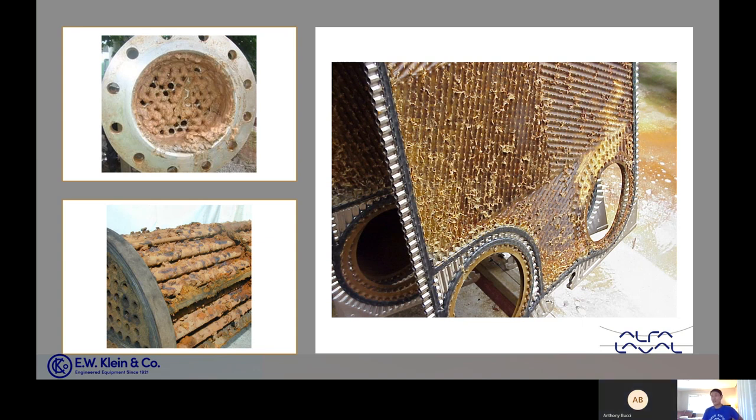So I actually had to clean some of these heat exchangers in my previous job. Like when it gets fouled up, they were tough. Like the ones I dealt with, it was like five feet long. So we had like five feet long full of tubes, full of gunk and gunky oil. It was tough to clean out, man. And if this gets fouled up on the shell side, I don't know. At least I didn't know a good way to clean it. It's like dropping it in a chemical bath and just let it soak. Let it soak. And just hopefully it'll dissolve and break it apart. But that was just, it's tough to clean a shell and tube once it gets fouled up.